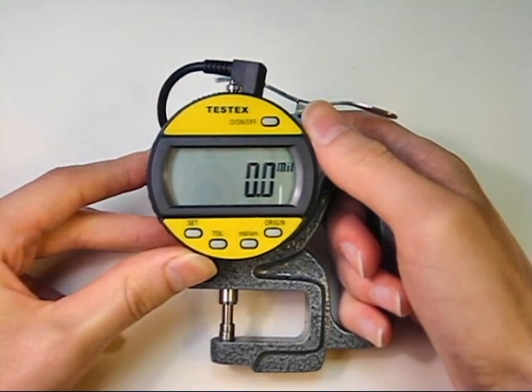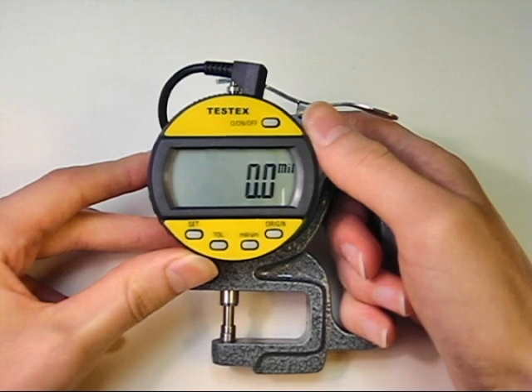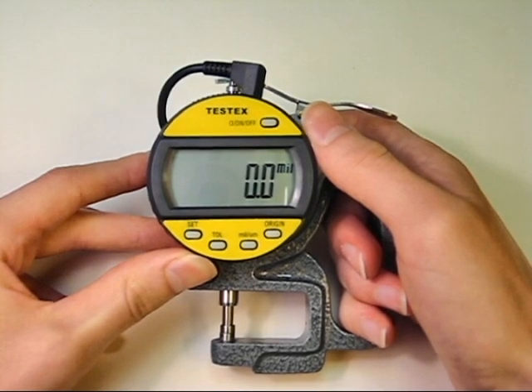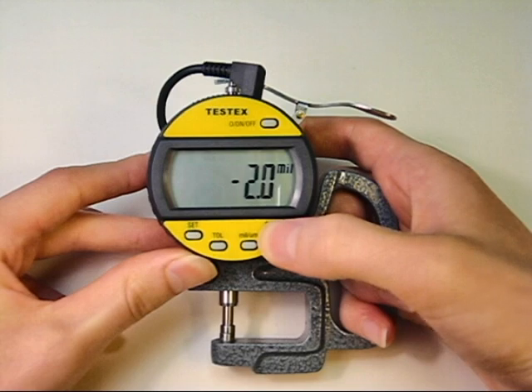Obtaining a measurement starts with turning the gauge on by pressing and holding the on-off button, then presetting to subtract the thickness of the replica film's incompressible layer. Presetting is done by pressing the origin button.